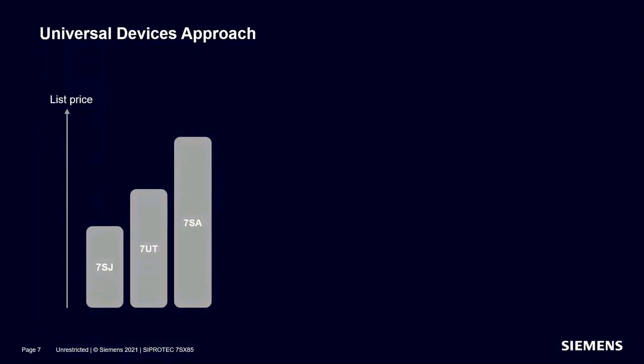Klaus introduced the flexible design of our SIPROTEC 5 family using modular hardware, the functional flexibility via the function library in DIGSI 5, and the concept of function points for customizing the SIPROTEC 5 relay according to the applications. The type-related devices, the 7SJ overcurrent relay, 7UT transformer protection relay, and 7SA distance protection relay, are using this flexibility already, but not yet to the possible maximum amount.